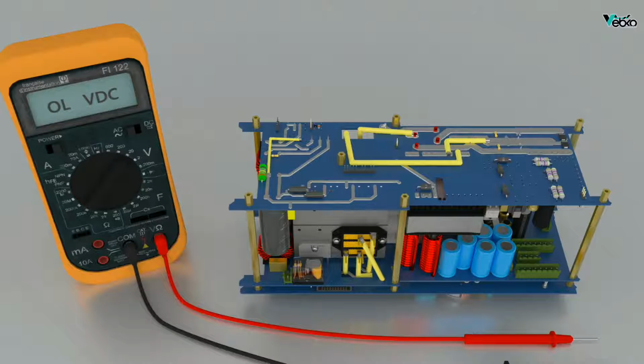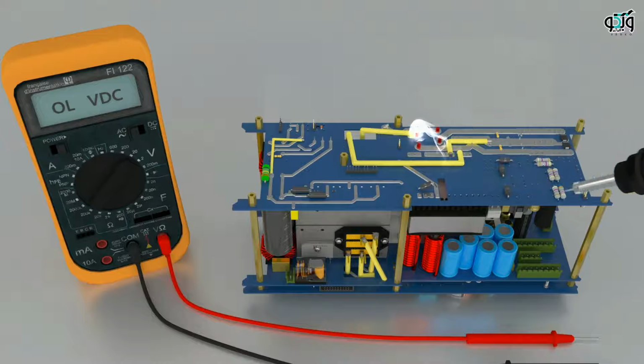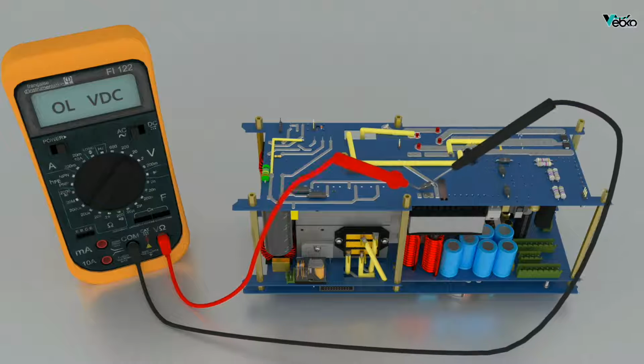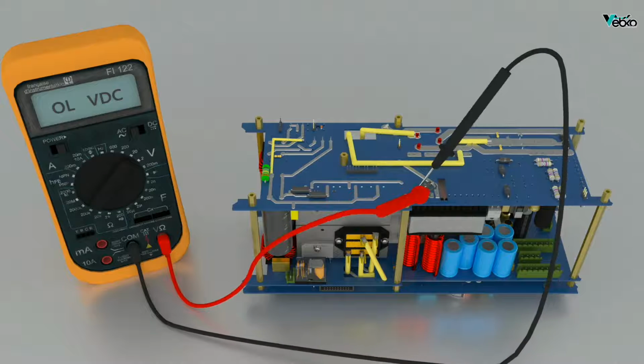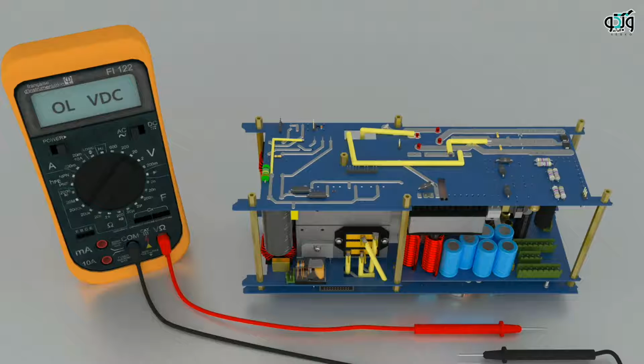Here there are 3 diodes to test. There are 10 diodes here and 2 other diodes that are located at the voltage and current output. First, following the instructions that were given earlier, detach one of the sides of the diode that is located on the 2 sides of the transformer. The diode test of this diode must show overload in both sides. If the drop of the voltage is displayed in one side, this diode is probably damaged. If the diode is overload in both sides, it is healthy.